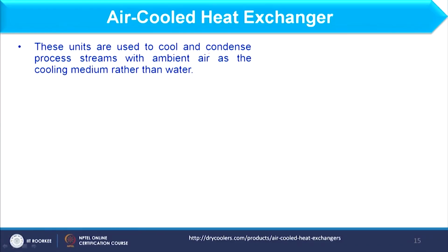Air cooled heat exchangers are used to cool and condense a process stream with ambient air as the cooling media rather than water. So usually for condensation purposes we use water, but here we are using air as a cooling media, and the second fluid will definitely be the vapor which is to be condensed.